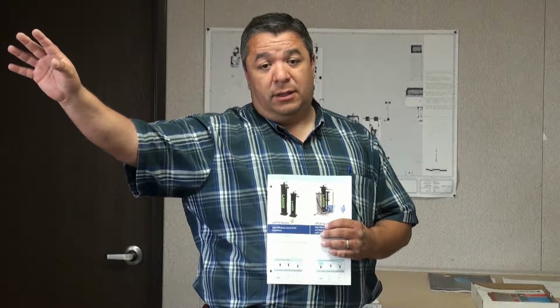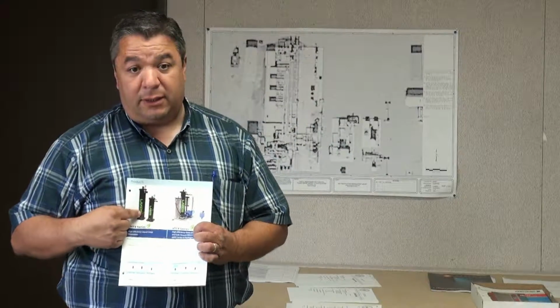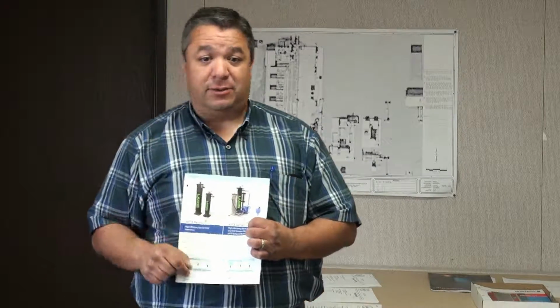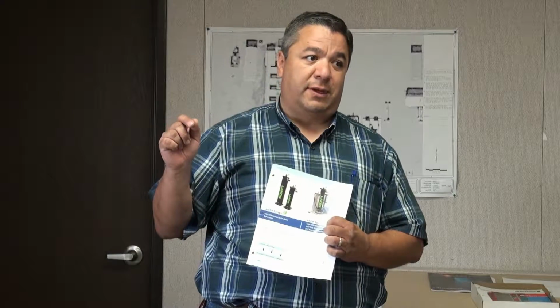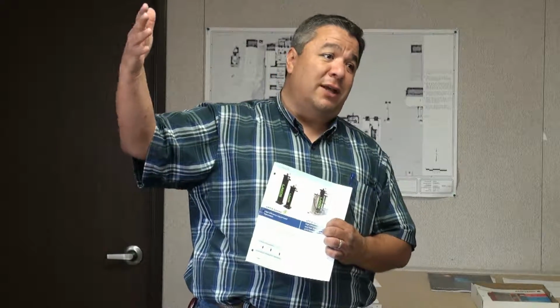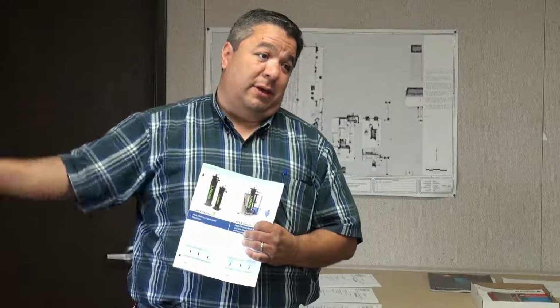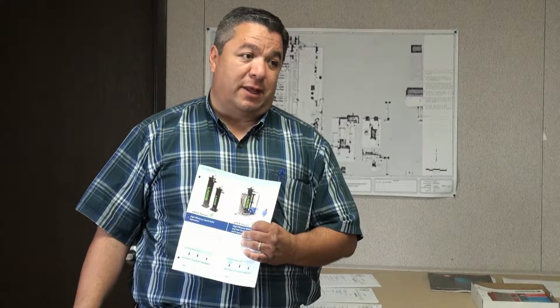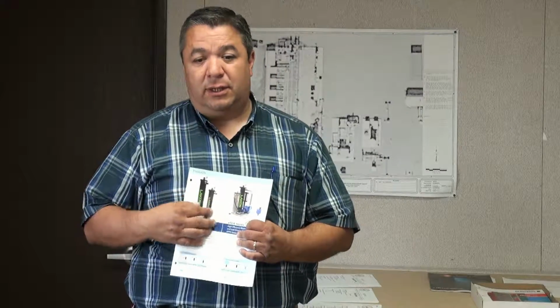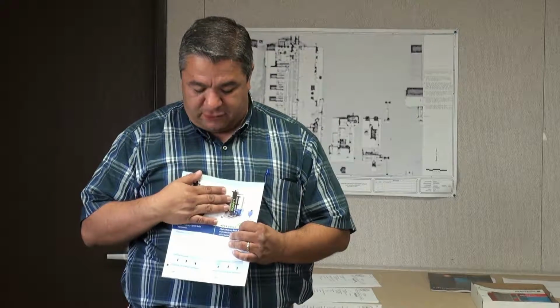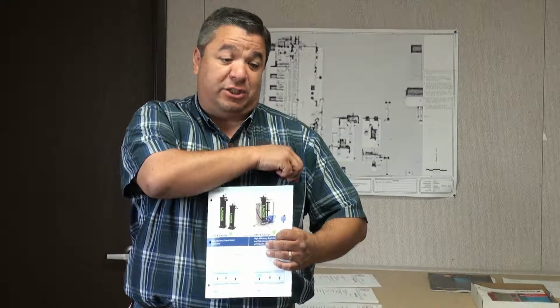What is it cleaning out the bottom of? Yeah, it cleans the bottom of the separator. In an automatic blowdown valve, there's no bag in the system anymore. There's just a valve. Okay. You've got a time relay, so you set it up for midnight for a minute, boom, throws it out. But people don't like wasting water, because every day you waste whatever water is popping out. That's just dependent on the size of the unit. So this one has a bag version of it. They do offer retrofit kits if you want to go in that direction, depending on how bad it is. They're not cheap.